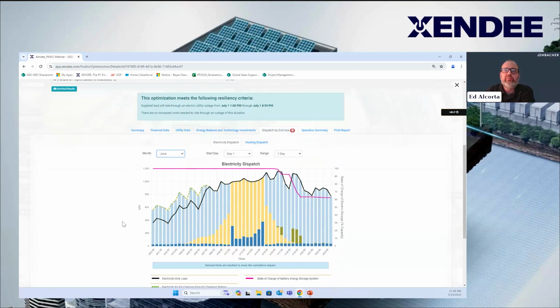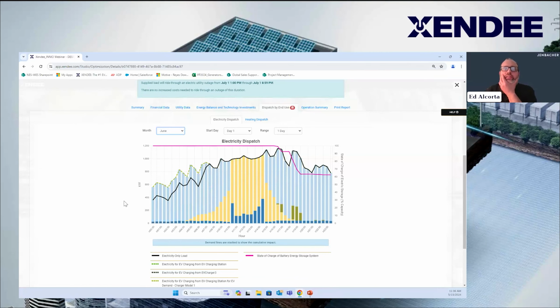There's a lot going on the screen at once: the light blue is what the Jenbacher genset is running at, the dark blue is utility import, which I forced at 5% at all times, not uncommon for behind-the-meter projects like this. The black line is the actual customer load profile, the green line shows EV charging added during off-peak times, the yellow is solar output, and the dark green is battery discharge, showing the state of charge of the battery.